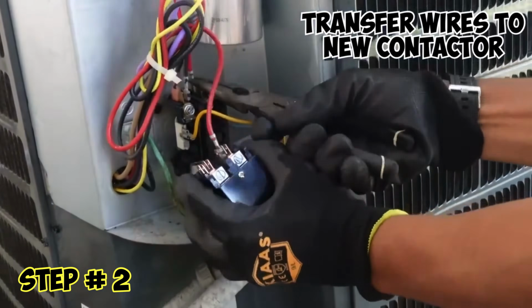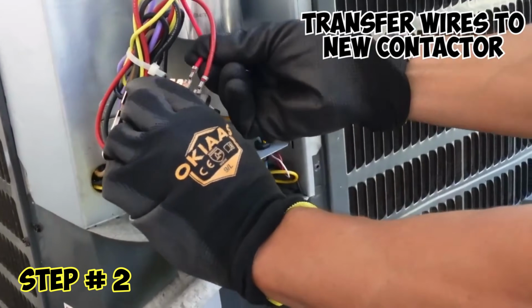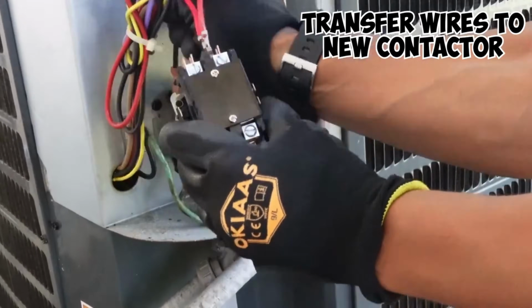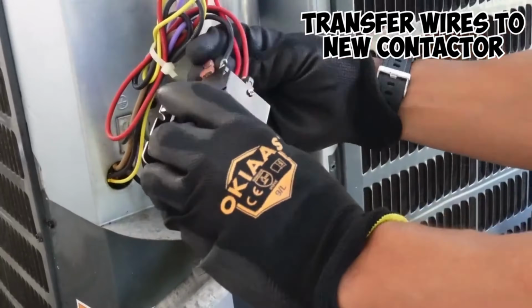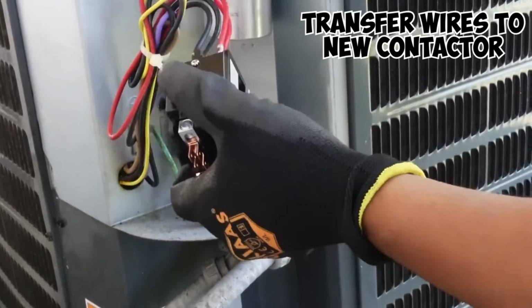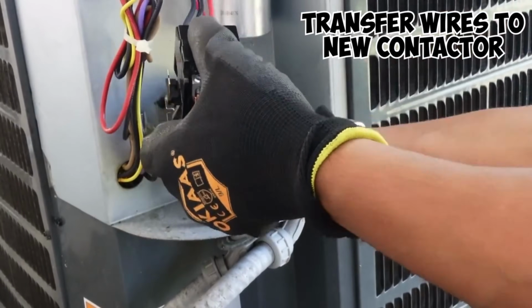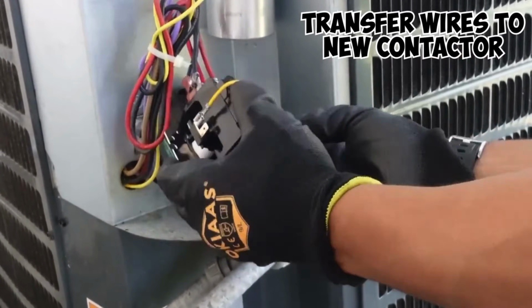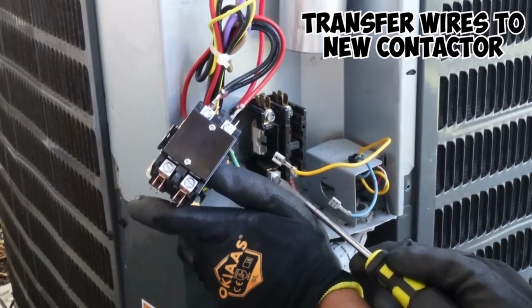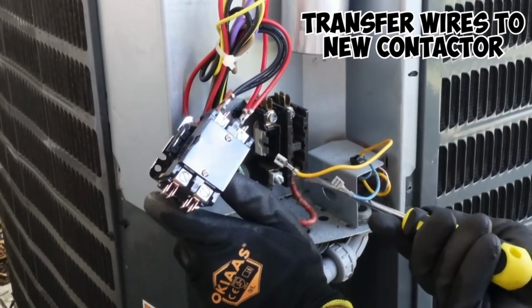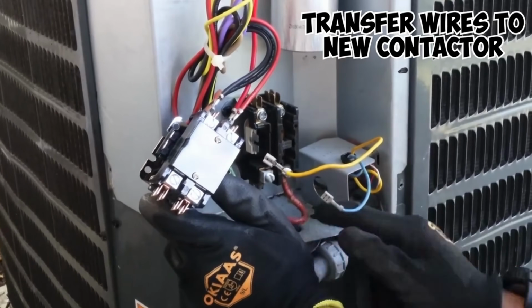The next step is pretty simple, pretty straightforward. You want to disconnect all the wires. I do recommend taking a picture of the setup so that you can put them back in the exact location. Or if you want to, you can disconnect the wires one by one and then connect them to your new contactor as you replace them. This is the integral part of connecting the contactor. Don't rush it, take your time.